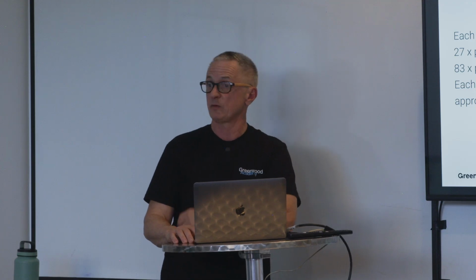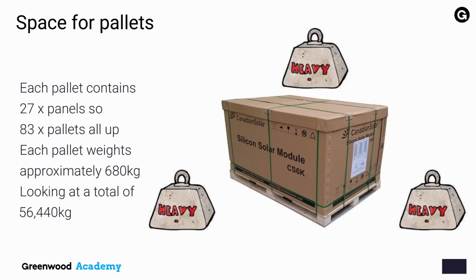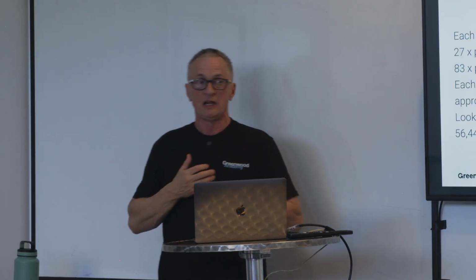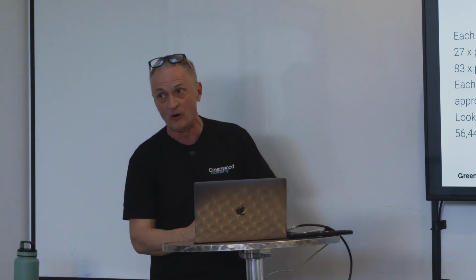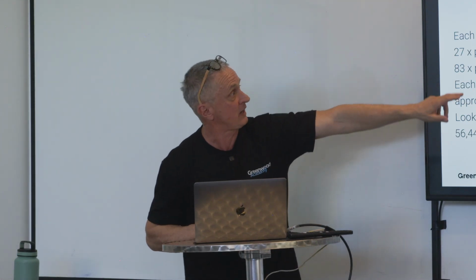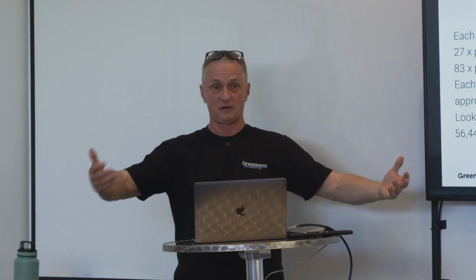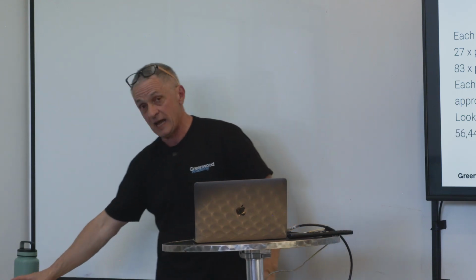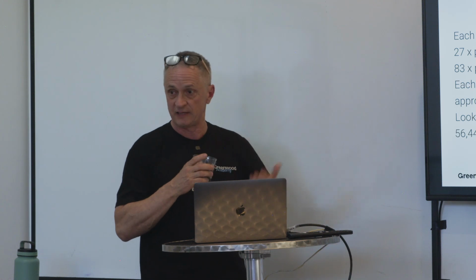Right. Now, as we said, there's other methods. We don't have to truck them up full, and that's a lot of weight. So straight away if you're lifting that amount, maybe GamCorp or whoever's going to charge you a little bit more, and maybe that cuts out 20% of the roofs that would support a sub 700 kilo pallet, because remember, these new roofs are designed so fine tolerance wise, and again, they're not designed to have anything on top of them. So take that into consideration.